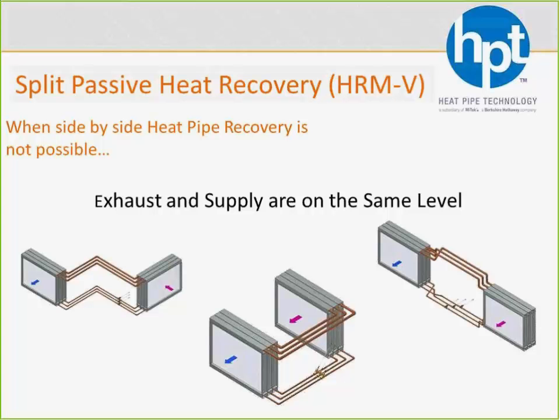Instead of 55% effectiveness, we're probably going to be closer to about 40% effectiveness, give or take. But if we split them apart, we can actually cross the lines so that counterflow, so you don't take that performance hit. With that said, it's worth noting that the HRM-V, because we're pulling those circuits to common headers and making them run a further distance, we do lose a little bit of performance. We're no longer at 55%. We're going to be closer to about that 40% effectiveness range as well.